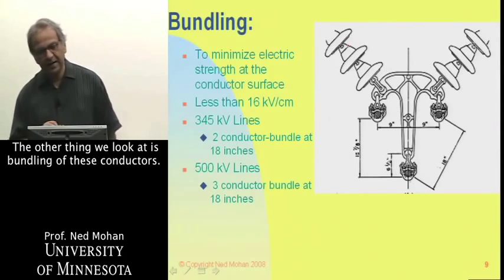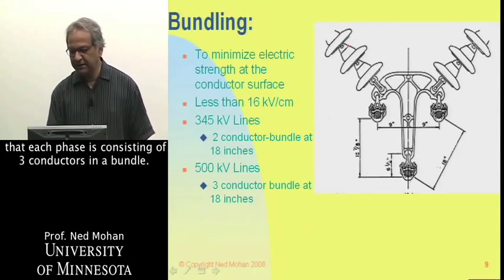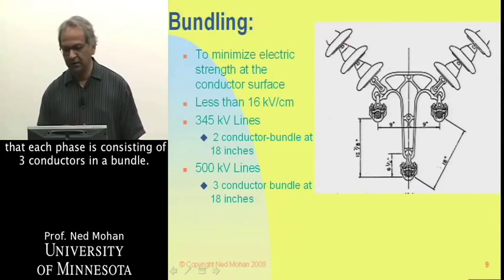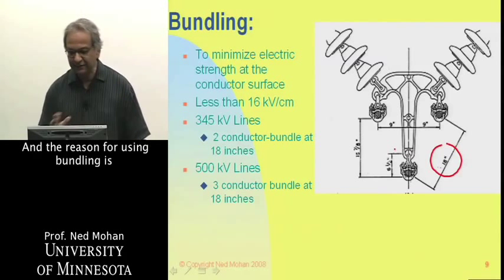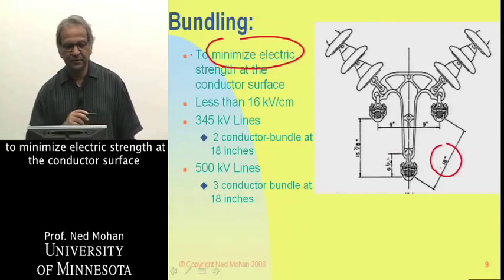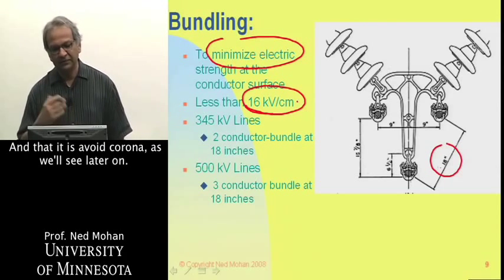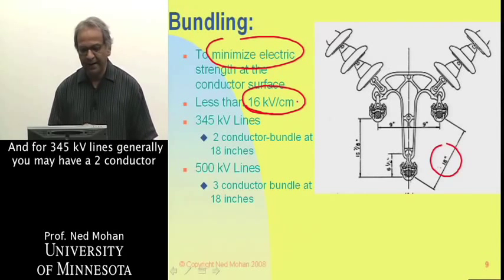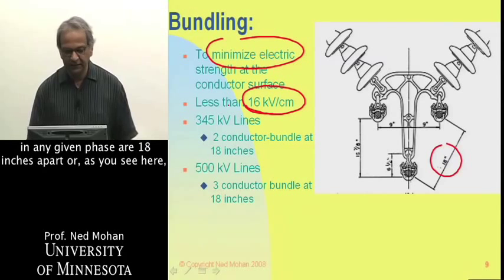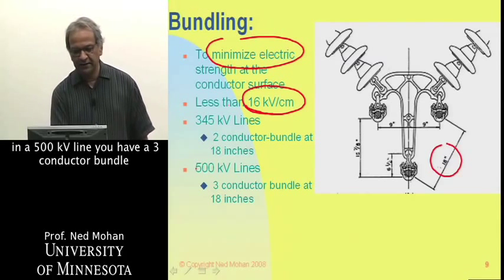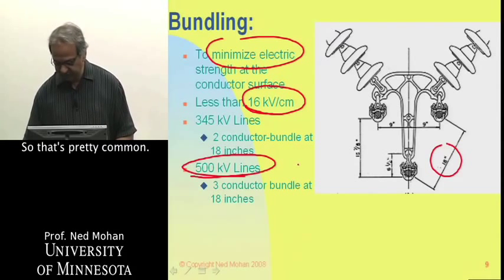The other thing we'll look at is bundling of conductors. In this 500 kV line, each phase consists of three conductors in a bundle, approximately 18 inches apart in a triangular configuration. The reason for bundling is to minimize the electric field strength at the conductor surface to less than about 16 kV per centimeter, in order to avoid corona. For 345 kV lines, a two-conductor bundle is typically used with conductors 18 inches apart, while a 500 kV line uses a three-conductor bundle.